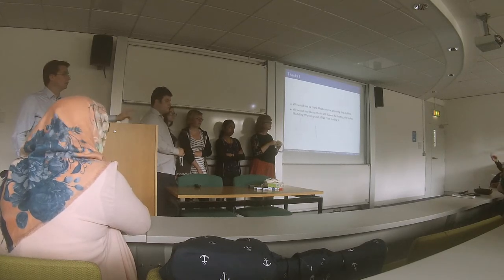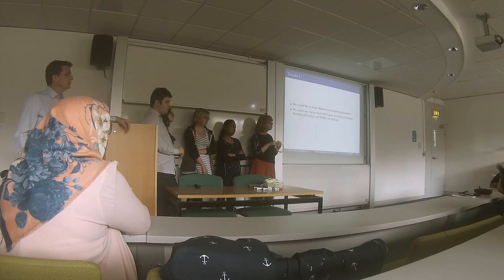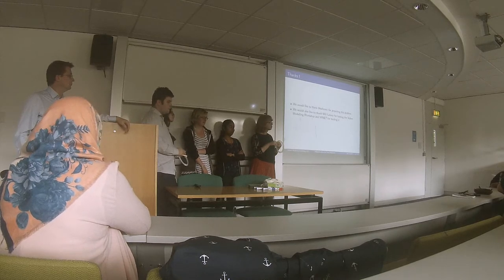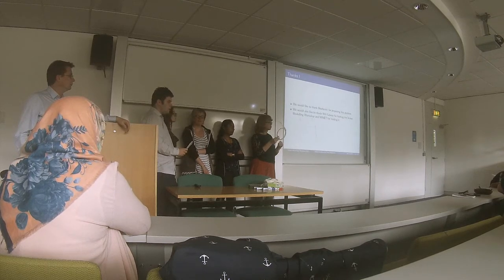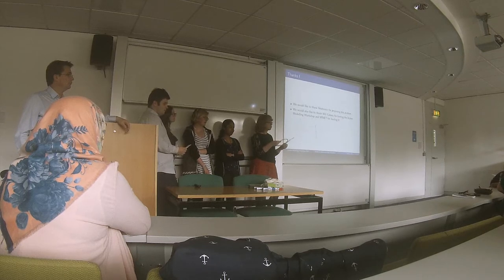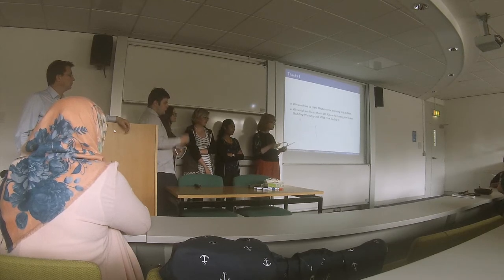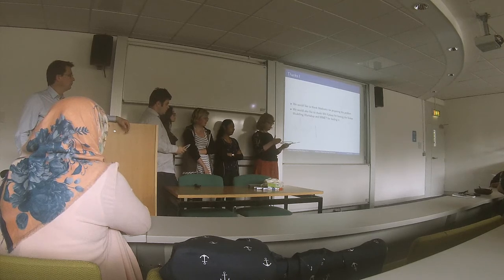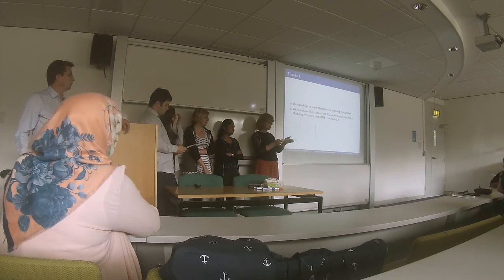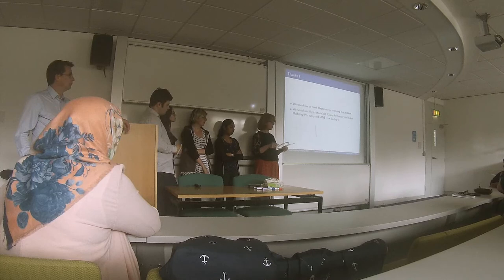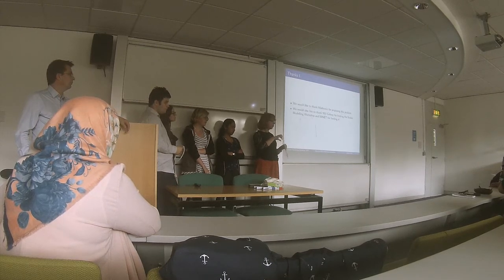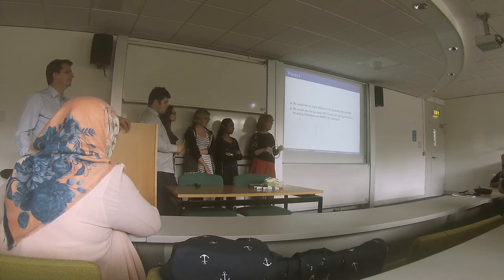Why don't they overkill it then and merge down on the deflection? Because it costs money. Yeah, and just space. Also the spacing for the packages, they have a certain square package and specific packages. And also if it bends too much, it would plastically deform and come out. You don't want that in your body.